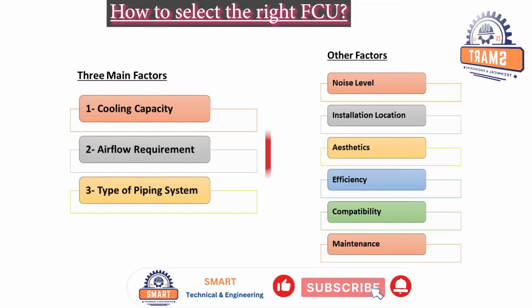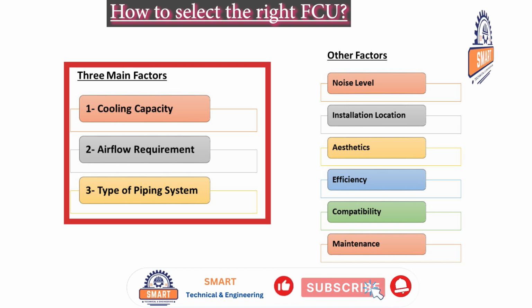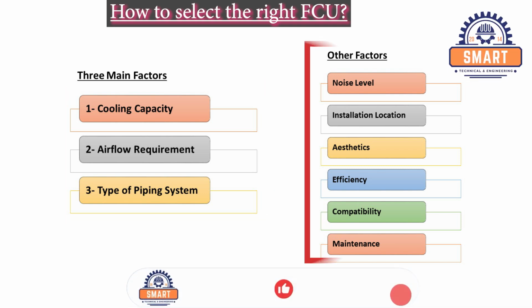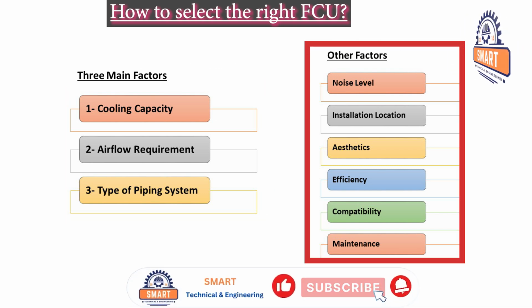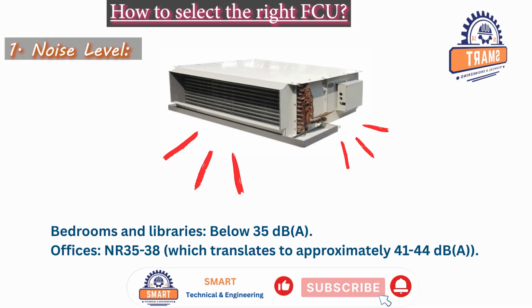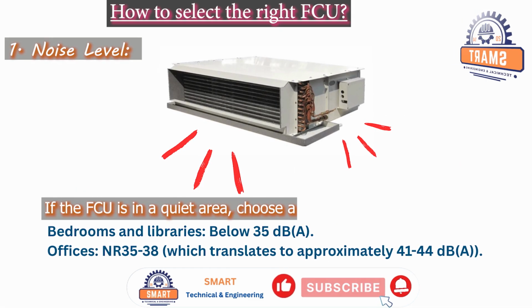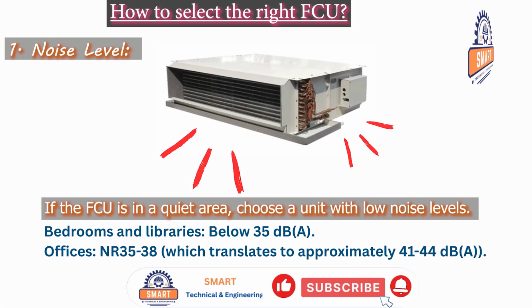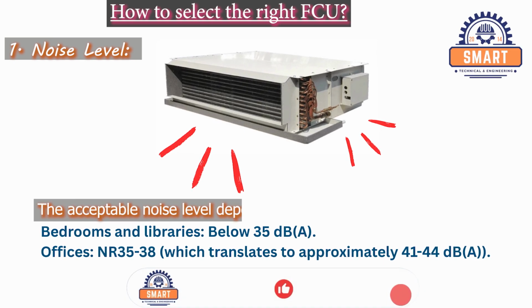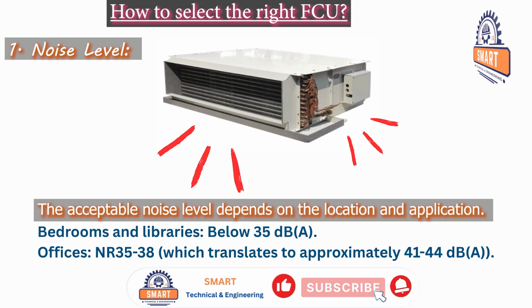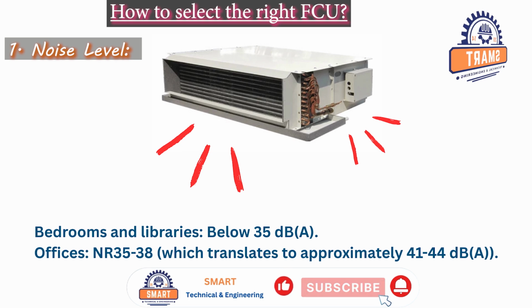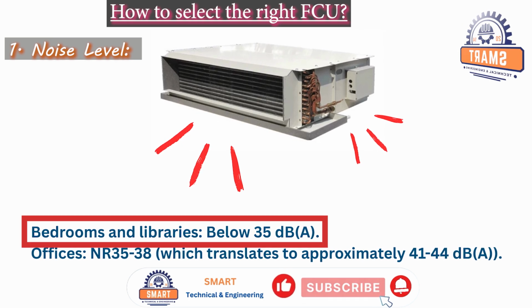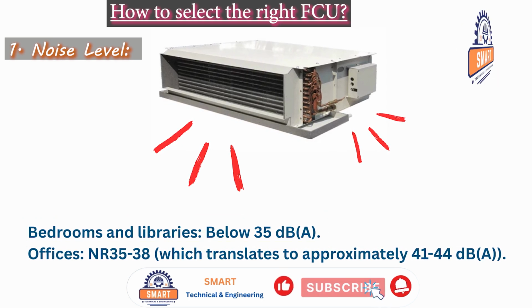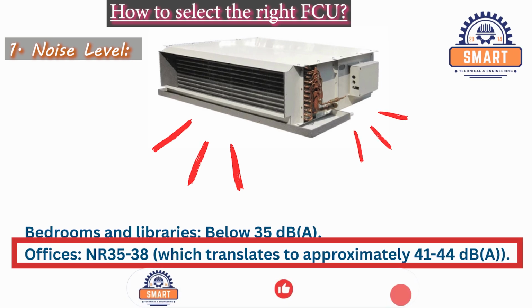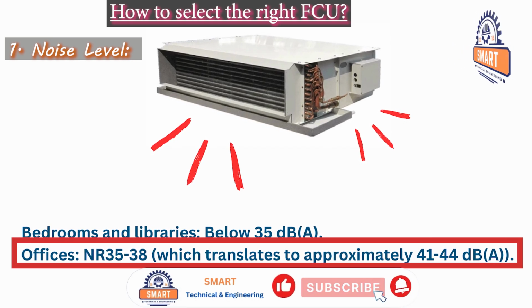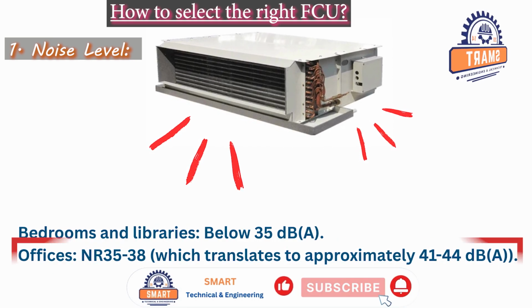After I described three main factors for FCU selection, let me continue to explore many other factors that are also important for the selection of FCU. 1. Noise level. If the FCU is in a quiet area, choose a unit with low noise levels. The acceptable noise level depends on the location and application. For example, bedrooms and libraries, below 35 dBA. Offices, NR 35-38, which translates to approximately 41 to 44 dBA.